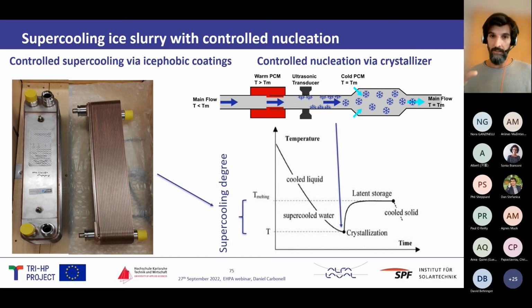The difference between the melting temperature and the actual crystallization temperature is what is called the supercooling degree, and the higher the supercooling degree, the higher the probability of freezing. So in order to have a stable supercooling degree, we have developed materials - icephobic coatings - that can delay the formation of ice, and we have applied this to real heat exchangers, brazed heat exchangers that are used in heat pumps as an evaporator.